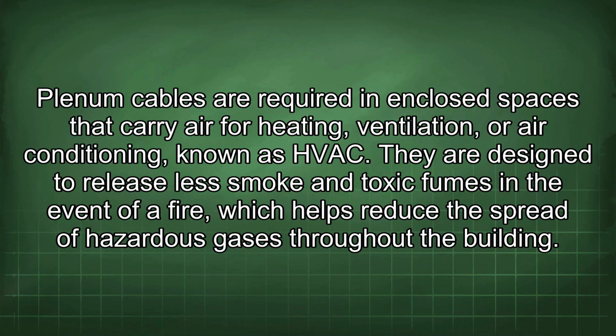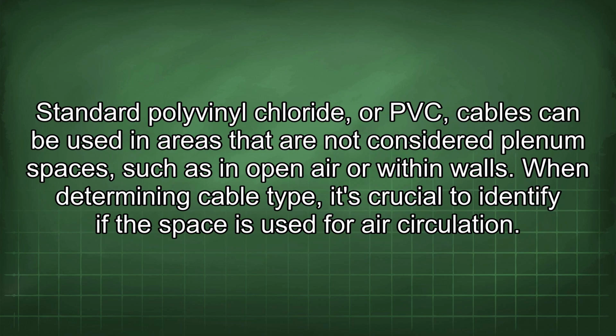Plenum cables are required in enclosed spaces that carry air for heating, ventilation, or air conditioning, known as HVAC. They are designed to release less smoke and toxic fumes in the event of a fire, which helps reduce the spread of hazardous gases throughout the building. Standard polyvinyl chloride, or PVC, cables can be used in areas that are not considered plenum spaces, such as in open air or within walls. When determining cable type, it's crucial to identify if the space is used for air circulation.